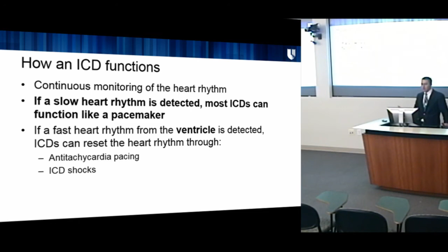In contrast to pacemakers, if an ICD detects a fast heart rhythm from the ventricle, it can reset the heart through one of two mechanisms. It can shock the patient, as we talked about, using the coils and the actual can or generator. In certain situations, the ICD can also pace the patient out of an abnormal heart rhythm by rapidly pacing the ventricle. Okay? So there's two different ways that the heart can be reset. The shock usually always works. That pacing mechanism, which we call anti-tachycardia pacing, works some of the time.